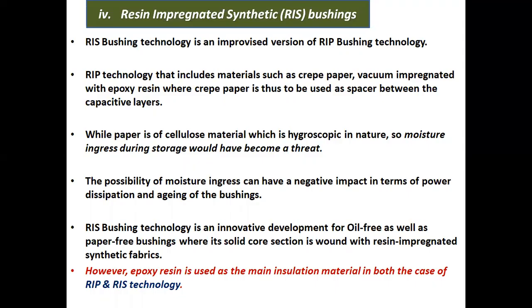While paper is a cellulose material, which is hygroscopic in nature, moisture ingress during storage would be a real threat. The possibility of moisture ingress can have a negative impact in terms of power dissipation and aging of the bushings. Resin impregnated synthetic bushing technology is an innovative development for oil-free as well as paper-free bushings, where its solid core section is wound with resin impregnated synthetic fabrics.